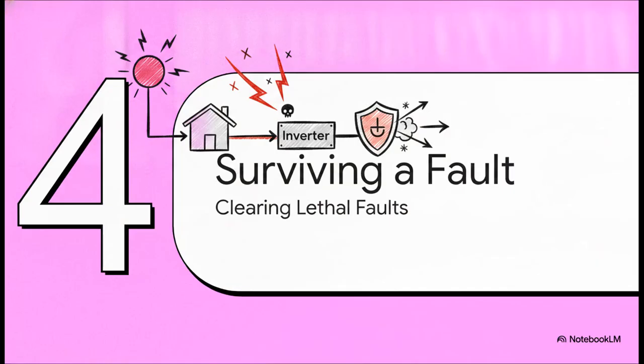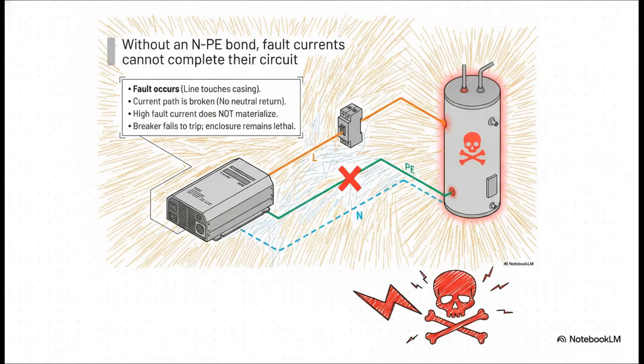Okay, part 4, surviving an electrical fault. So what does this all mean in the real world? Let's simulate a worst-case scenario. Imagine we have an earthed system, but we forgot the NPE bond. Now, say a line wire accidentally touches the metal casing of a water heater.